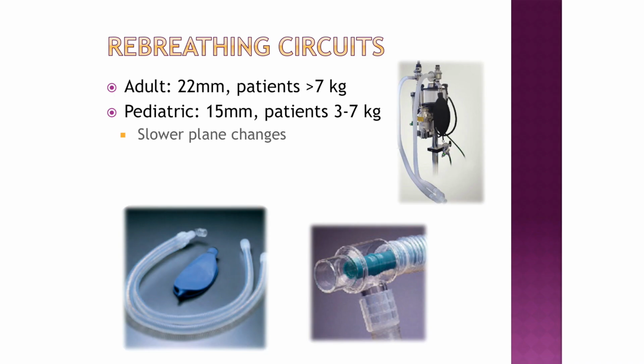The adult circuits, so 22 millimeters for patients more than 7 kilograms. We talked about that. But the circle systems are going to be associated with longer plane changes, right? Because I have to fill this 5 to 7 liters worth of space and turn my oxygen flow up pretty high in order to make a rapid plane change, versus my non-rebreathers. All I'm doing is blasting gas to their face and taking it into the scavenger. And so we're going to see much more rapid plane changes.